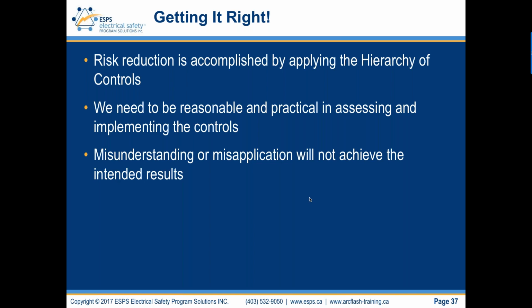This is critical. If you misinterpret and misapply the process and the information that you feed into it, your results will be skewed and potentially very conservative, and everything will be high risk. So I guess you have to shut down doing any energized electrical work in your company, which isn't reasonable and isn't practicable in the eyes of the OH&S regulations. Again, another misinterpretation is that it's against the law to work energized. That's being communicated in Ontario, unfortunately, here in Canada, and it's completely a lie.